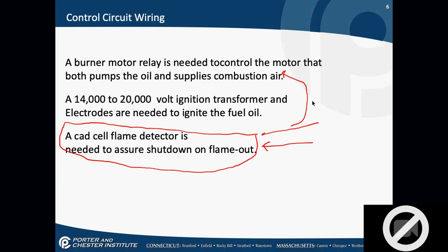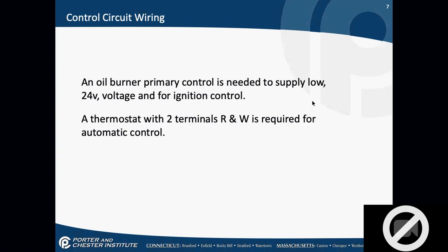Okay. CAD cells don't last forever. They're a primary source of failure if they start getting soot or smoke onto them. That's why having such a clean flame and a clean burning flame is important. The electrodes contribute a lot to the clean flame. An oil burner primary control is needed to supply the low voltage for your thermostat and the line voltage for ignition control. A thermostat with 2 terminals is required for automatic control. 2 terminals for heating, R and W.